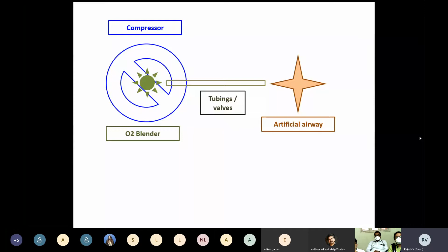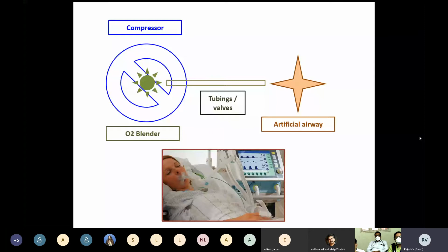In addition, you have a monitor which gives you parameters of how the ventilator is delivering the breath, how the patient is taking it, and how the patient's parameters are. All these things can be monitored and displayed so that the caregiver can adjust the settings accordingly. As I said, there's the compressor with settings, which generates a breathing mixture under pressure. The clinical utility of this is that it obviates the work of breathing. The patient doesn't have to perform his inspiratory work. And the breathing pattern can be decided due to the presence of tubings and valves.